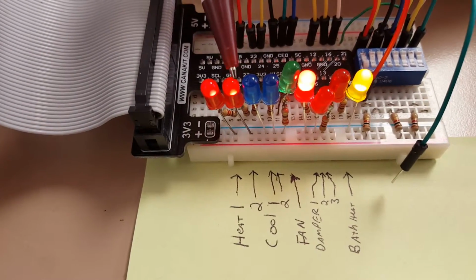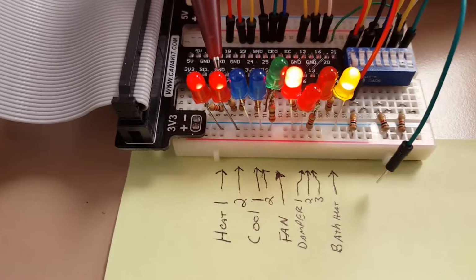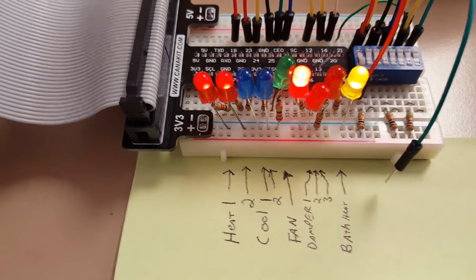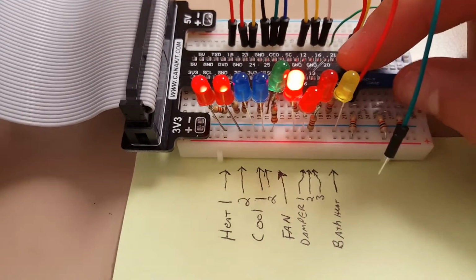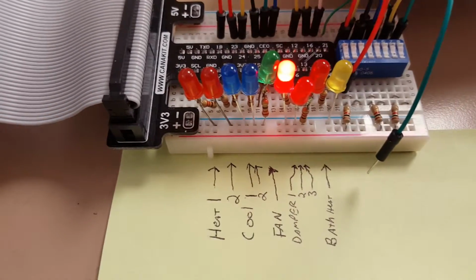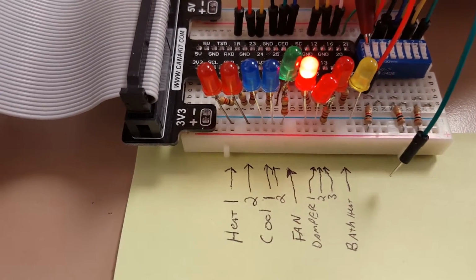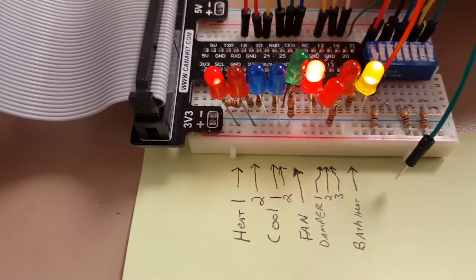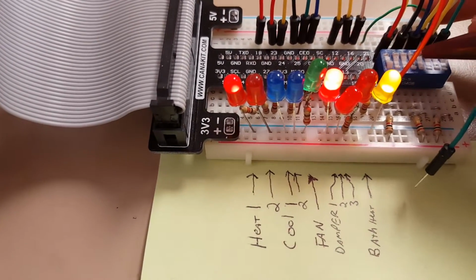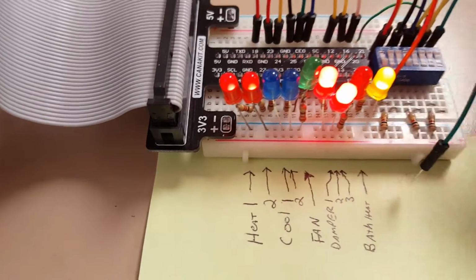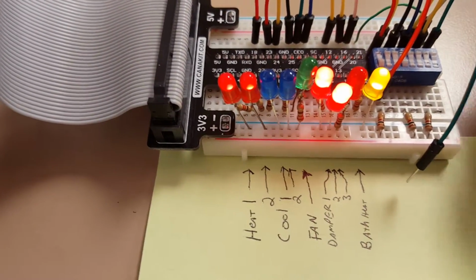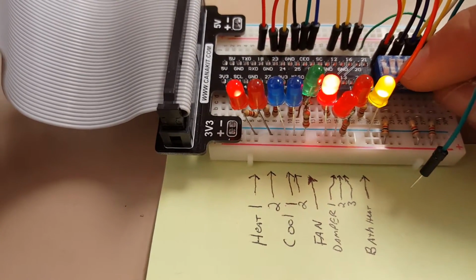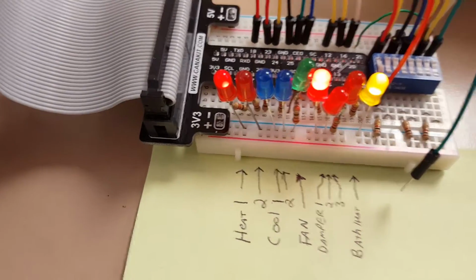You'll see the second stage heating came on, and that's going to happen anytime a given amount of time elapses, probably 15 minutes. Or similarly, I'll turn that off there and turn it back on. So now we're back to one zone. Before that time elapses, I'll call for another zone. So if 2 zones are calling for heating, we'll get 2 stages of heating, or if that time lapse has occurred.